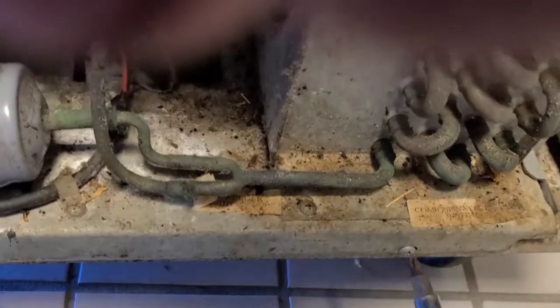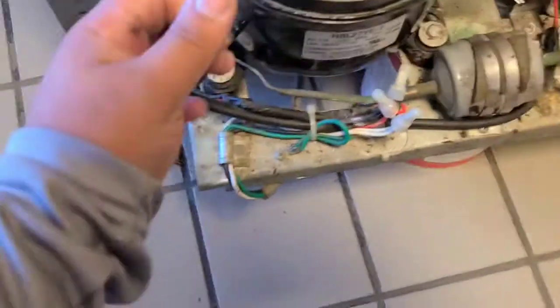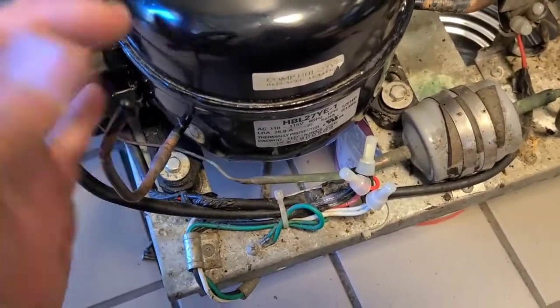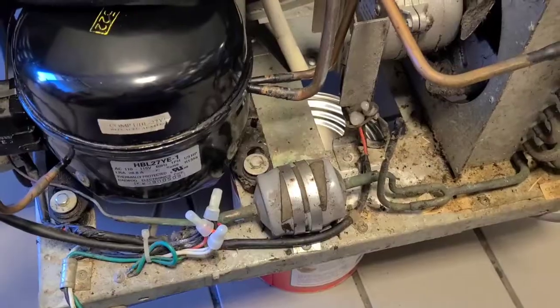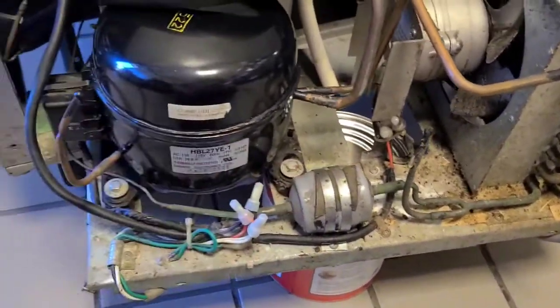All right guys, I'm back to replace this compressor. Start getting this refrigerant out. I slid it out — there's no ports on here, so I'm just going to cut it, braze a little port on here, open that up and take whatever's in it out, then start getting everything out and change this filter dryer and the compressor.